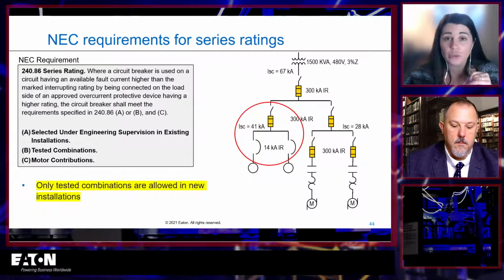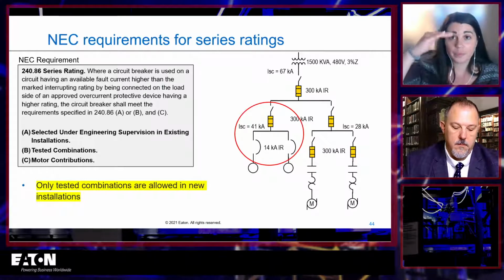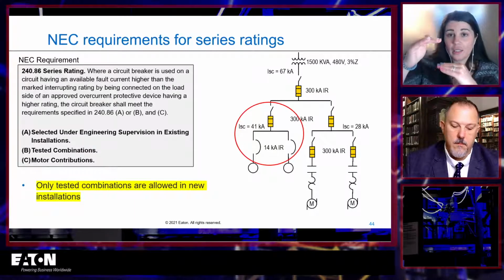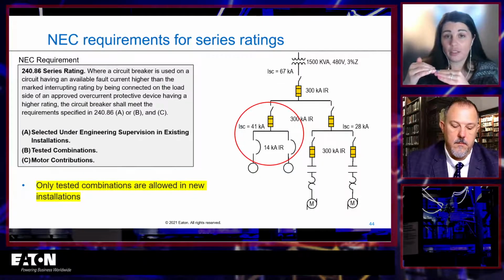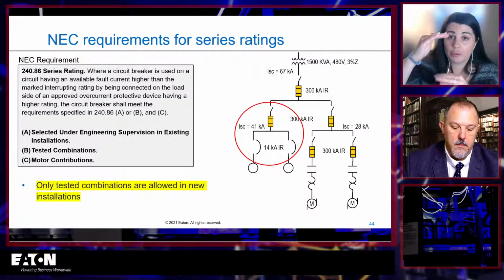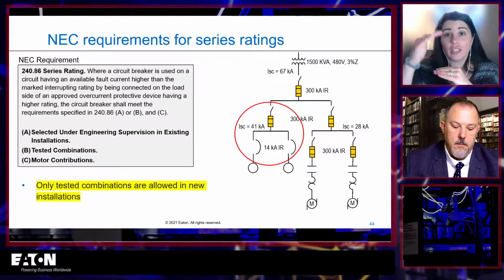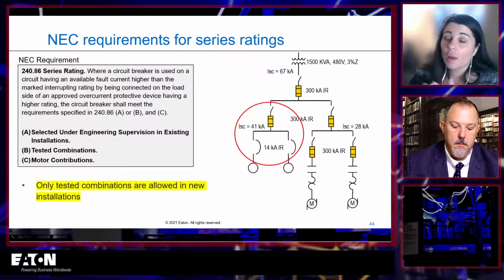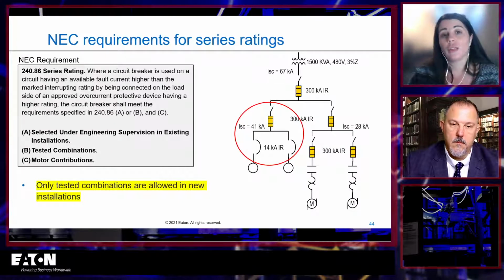So series rated, right, this is when you have a higher rated device and a lower rated device, and the available fault current at the lower rated device is higher than its rating. Then hopefully you use the higher rated upstream device to make this series rating with the downstream device. And there are a couple of requirements you have to meet in order to do this.